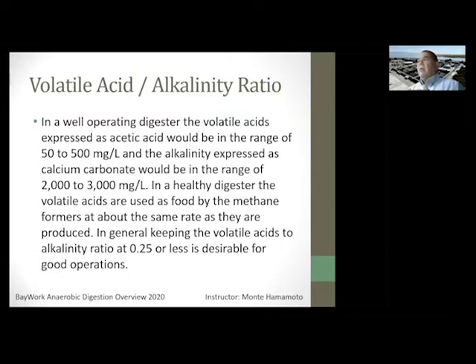So if you do a division, take your volatile acid concentration and divide it by your alkalinity, you should have a ratio, and you want to keep that ratio as close to 0.25 or less. That means you have plenty of alkalinity to handle any big shots of volatile acids that you might have. It has plenty of buffering capacity, so it won't affect your digester.